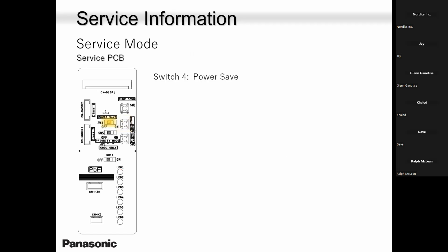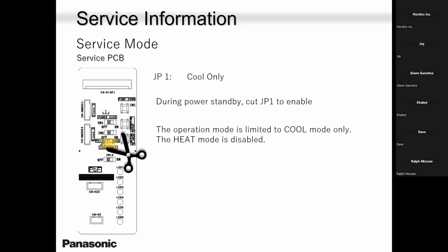Power save function is there. Basically, you're lowering the capacity by 75%. I'm not a big fan of that power save. But again, if you have oversized the outdoor unit, that's fine. You can reduce the capacity by flipping that SW4 power save button on the other side, so it does not run very hard. These heat pumps also are equipped with a jumper, JP1. Basically, if the homeowner says, I'm buying this multi-zone only for cooling, you can chop off that piece of wire. Now you are in cool mode only.